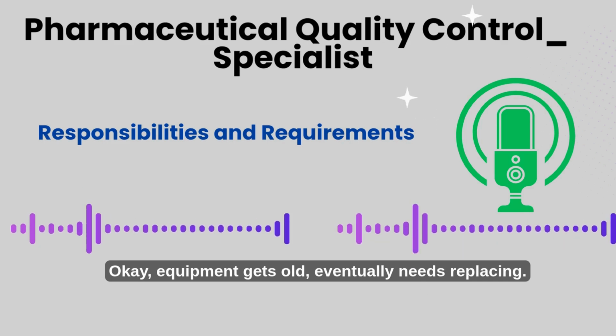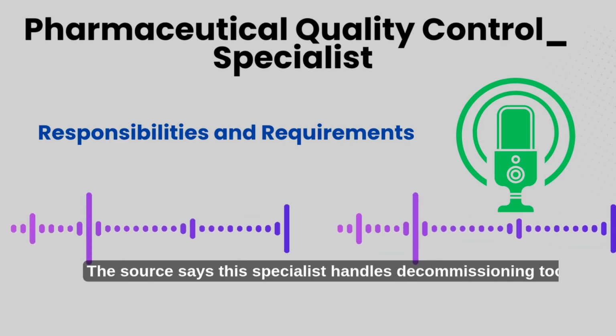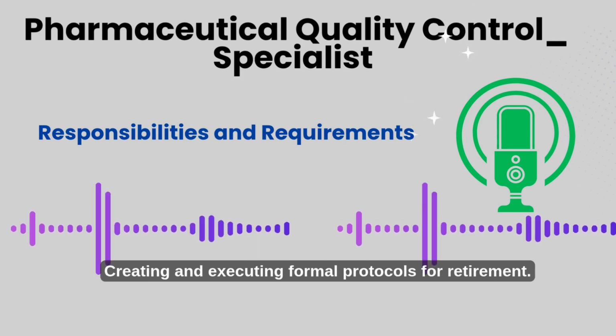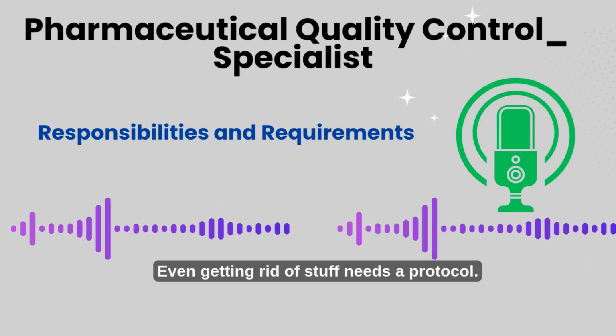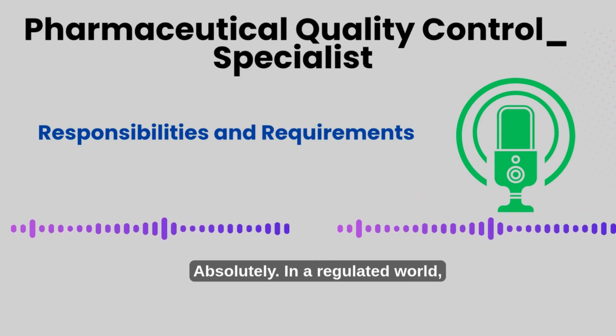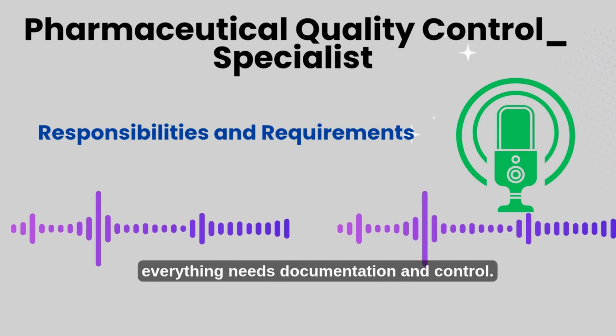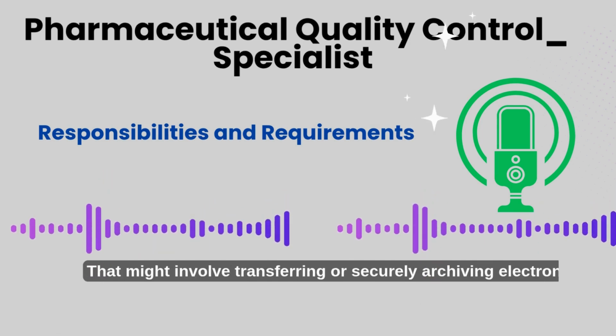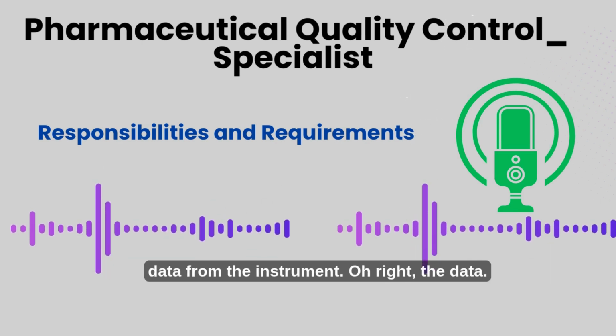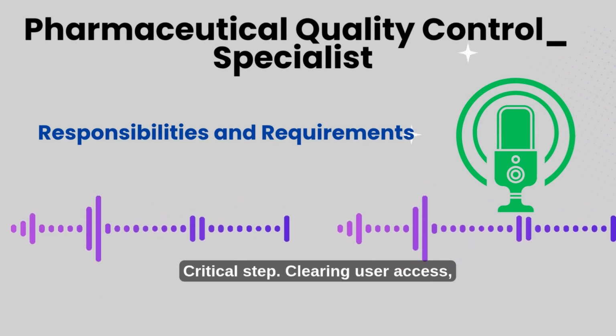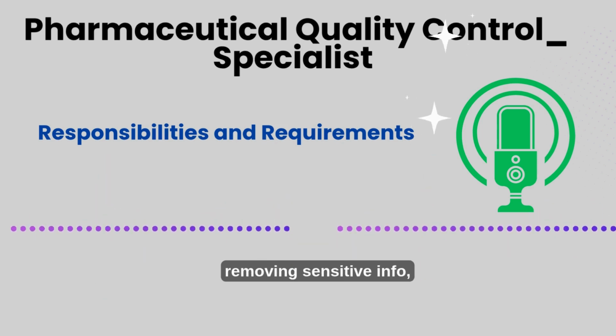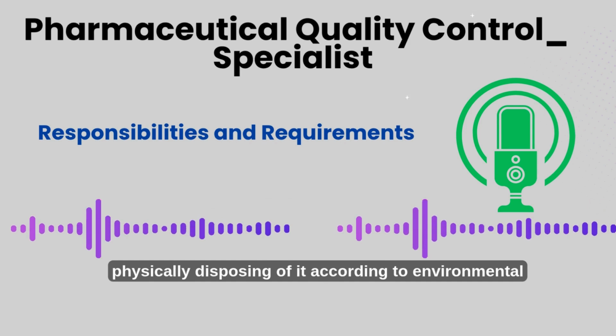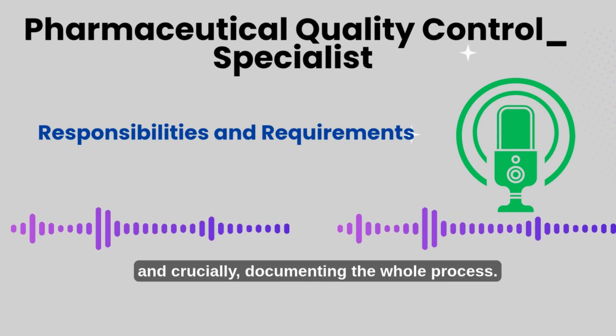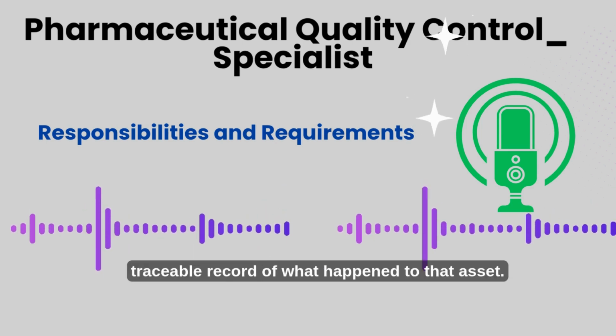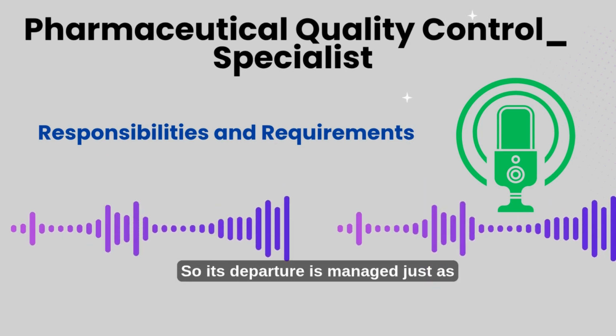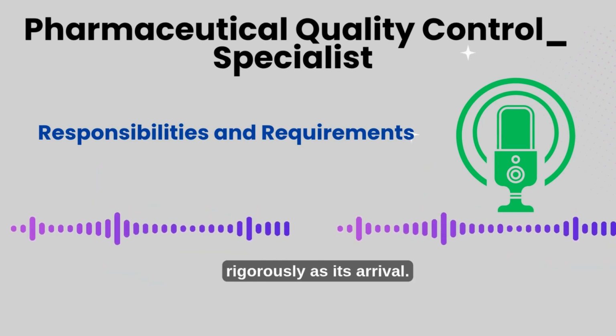Okay, equipment gets old, eventually needs replacing. The source says this specialist handles decommissioning too, creating and executing formal protocols for retirement. Even getting rid of stuff needs a protocol. Absolutely. In a regulated world, everything needs documentation and control. A decommissioning protocol ensures it's done properly. That might involve transferring or securely archiving electronic data from the instrument. Oh, right, the data. Critical step. Clearing user access, removing sensitive info, physically disposing of it according to environmental rules, and crucially, documenting the whole process. You need a clear, traceable record of what happened to that asset. So its departure is managed just as rigorously as its arrival.